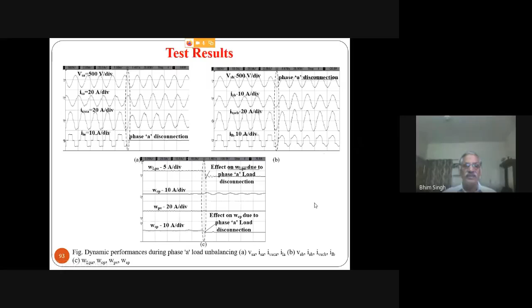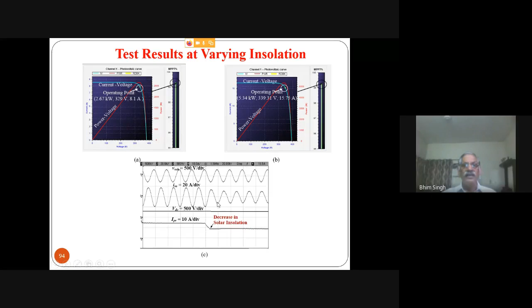Like, and during this dynamics of load change, because the active component of current in the load reduces, the second harmonics get reflected, so that goes into the DC-link and other components also, and this is virtually how the dynamics take place. The dynamics do not take hardly more than a cycle. You can clearly see when solar power generation is changing, hardly half a cycle is enough for the whole dynamics.